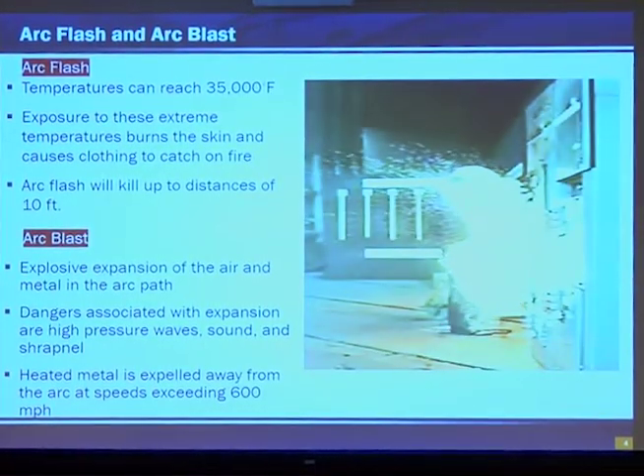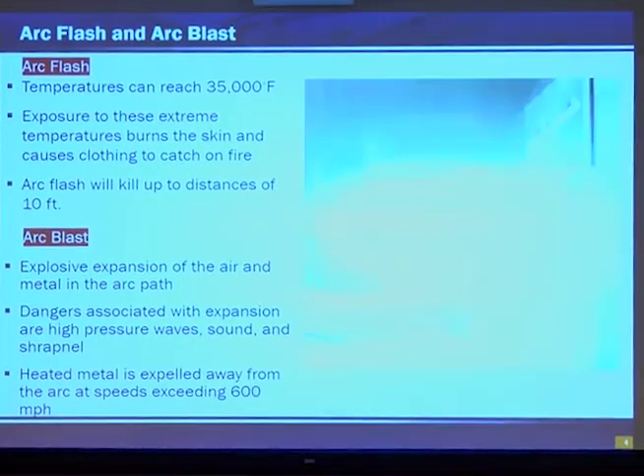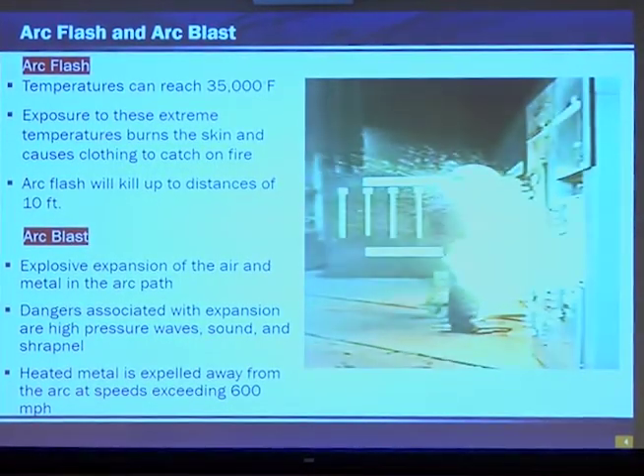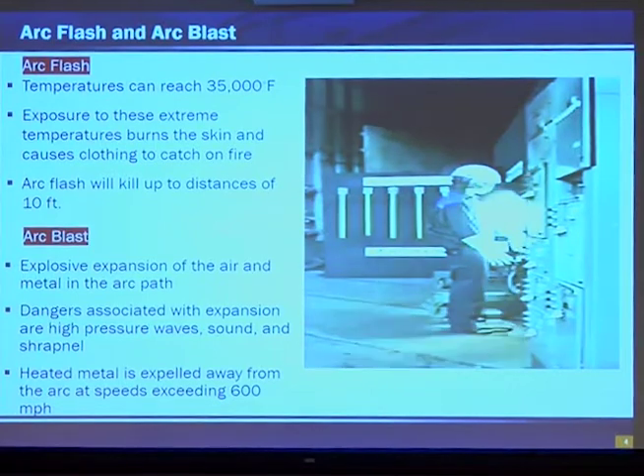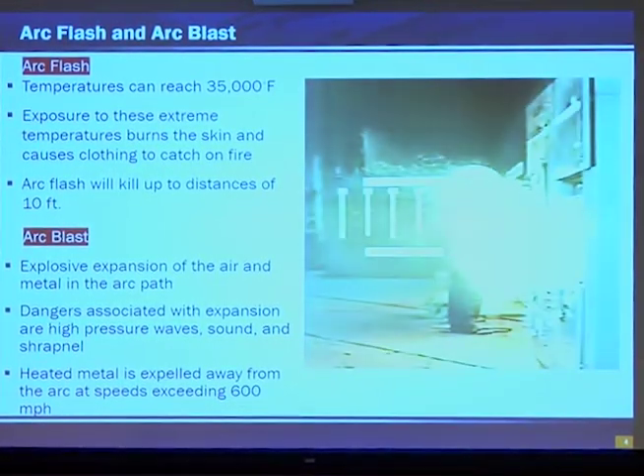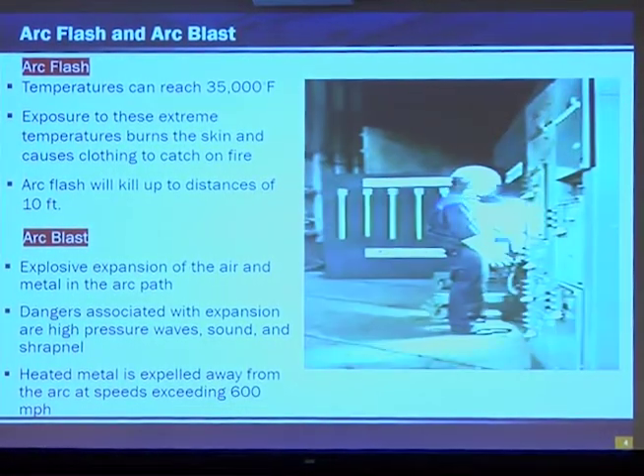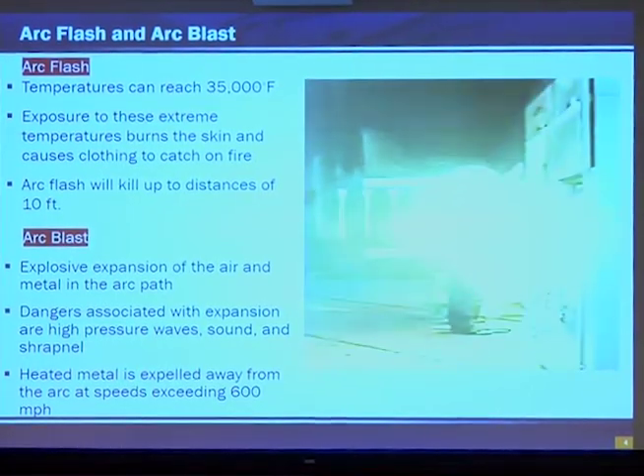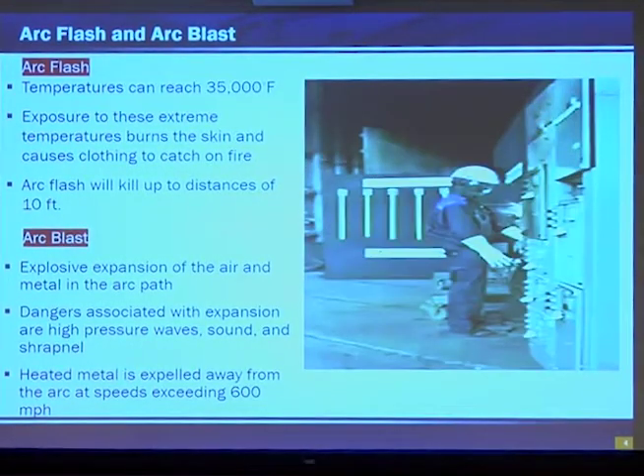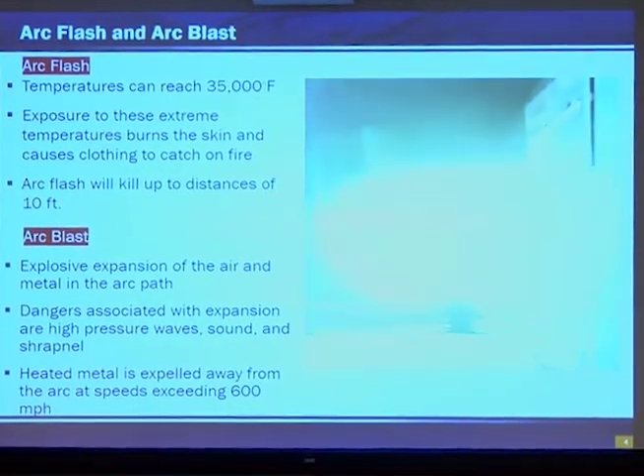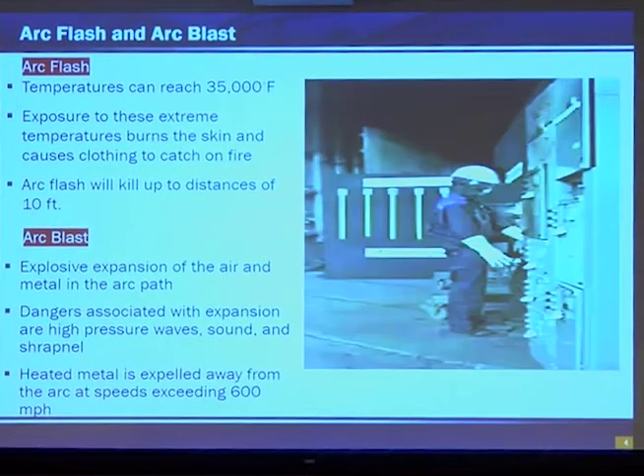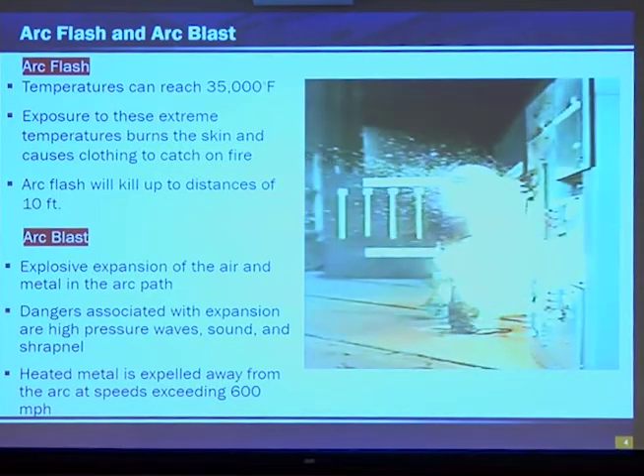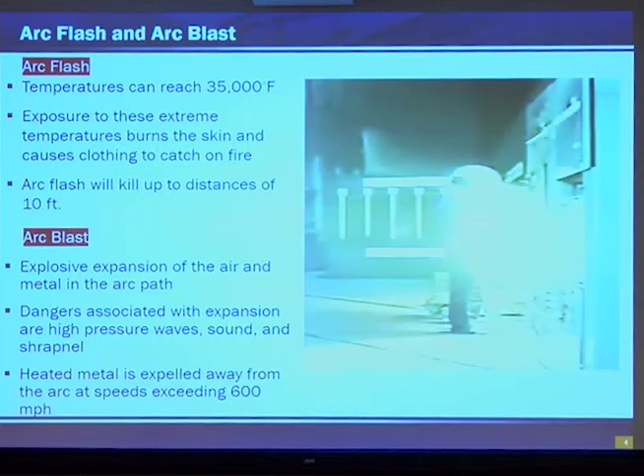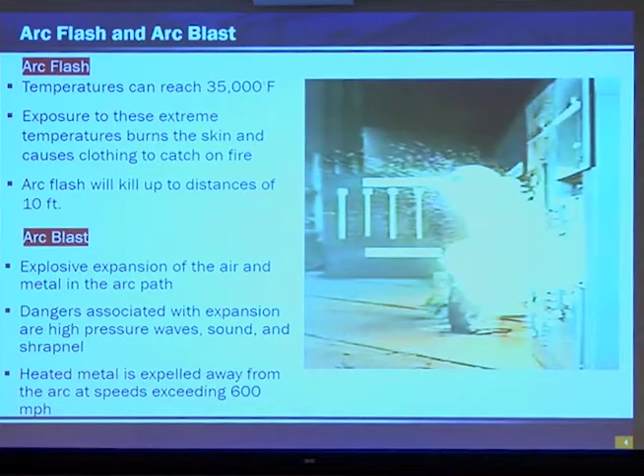Now, the arc blast is the explosive expansion of both the surrounding air and metal in the arc path. During that arc, copper expands by a factor of 67,000 times, turning it from a solid to a vapor. This is very similar to an explosion caused by dynamite. Now, there are three dangers associated with this expansion. They are high pressure waves, sound, and shrapnel. The pressure waves can easily knock workers off ladders. The loud sound can rupture eardrums. And the metal that's expelled away from the arc can penetrate the human body.